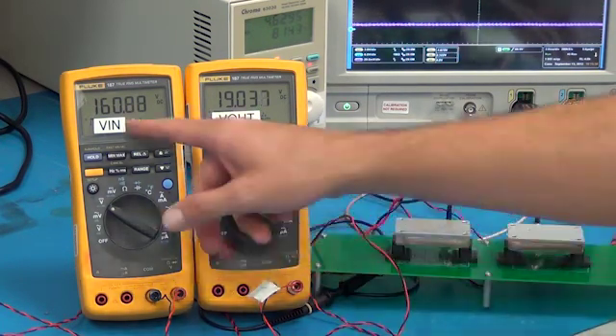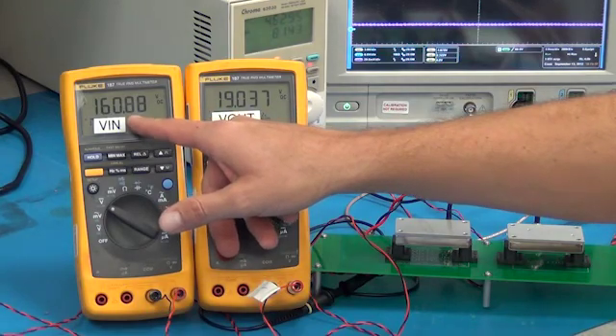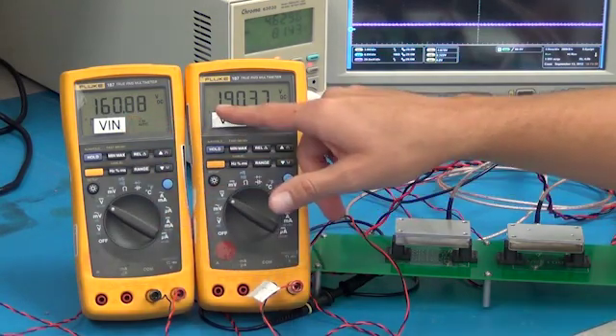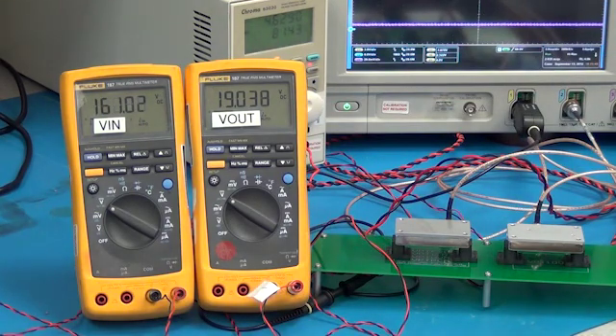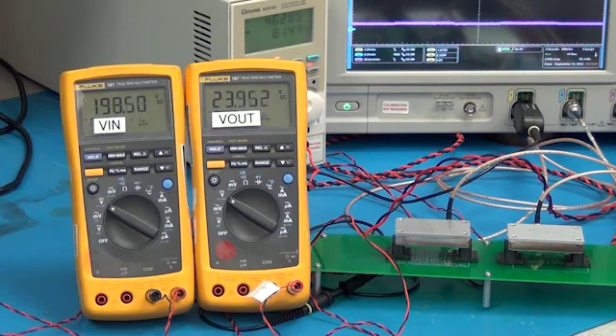For this demonstration I have 160 volt DC input to the HVM and in this case I have 19 volts output. As I increase V in you will see that V out will increase. This is all within the limits of our 28 volt standard product line.